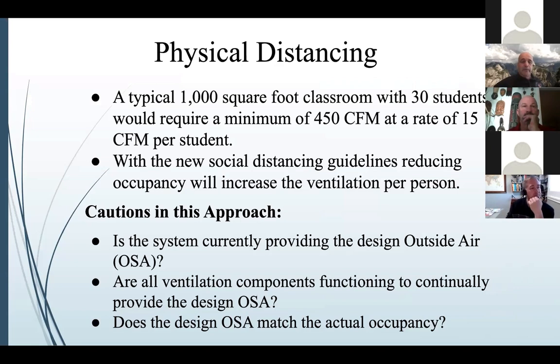because we have to keep people separate from one another. So anytime you reduce the load, for example, in a classroom where you reduce from 30 students to 15, if everything's working like it's supposed to, you've essentially doubled the ventilation rate and kind of met the guidance coming from the CDC and ASHRAE as it relates to increasing ventilation by cutting your load in half. The only downside to this approach is you have to be really careful to make sure that your system is providing the minimum air, the outside air. OSA is outside air. So first you have to test your system, make sure it's providing plenty of outside air. And if you cut your occupancy load down, you'll get increased ventilation just by cutting your occupancy load.